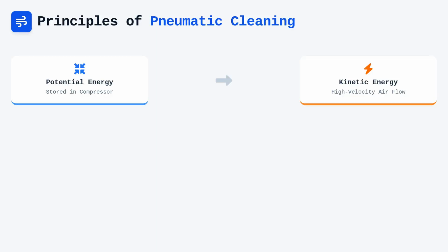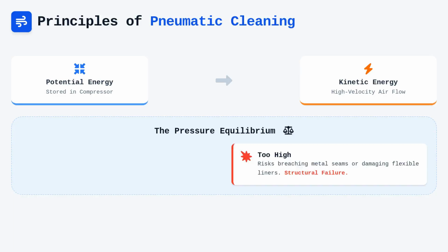When we deploy a pneumatic whip or an air skipper, we are essentially converting stored potential energy in the compressor into kinetic energy at the tool head. It is vital to understand that the air pressure, measured in pounds per square inch, must be balanced against the structural integrity of the ductwork. If the pressure is too high, you risk damaging flexible duct liners, or even breaching the seams of metal ducts, which defeats the purpose of system restoration.